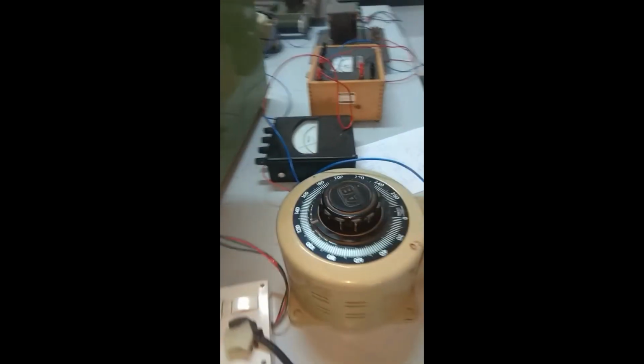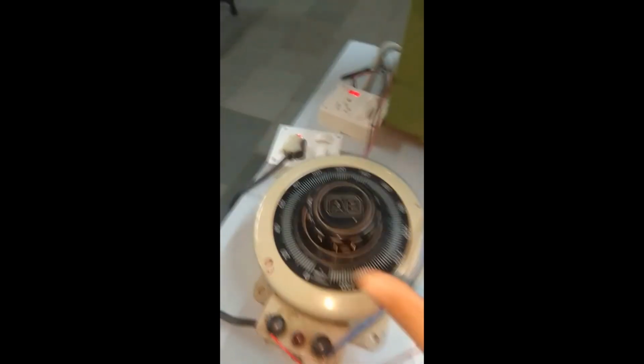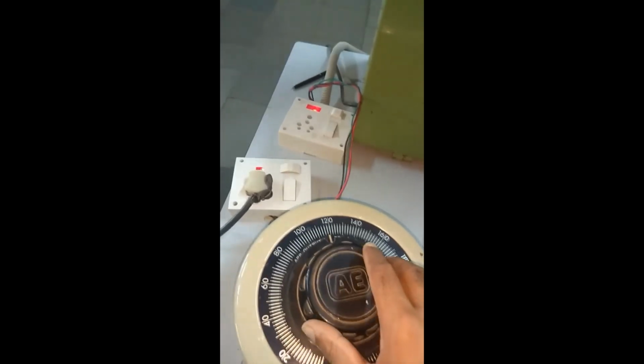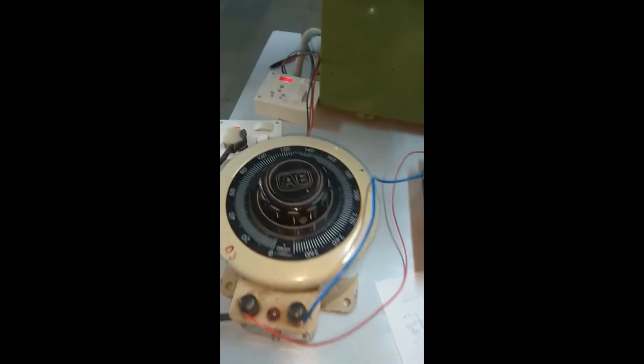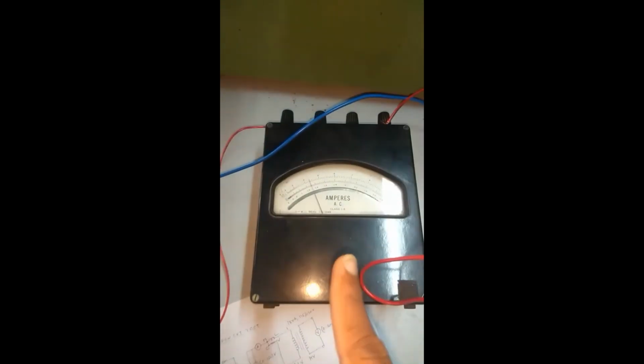Let's switch it on and see the reading. Now supply is switched on. This test is performed on rated LV voltage, so we need to set the voltage by varying this to 115 volts. This is connected. You can observe there is some deflection in the ammeter, as well as some deflection in the wattmeter - the needle has moved from its zero position. Please remember, do not touch any live wire while conducting this test or while taking the reading.